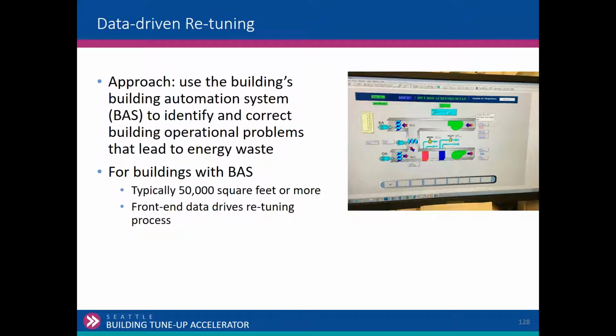So you've got observation-driven and data-driven. Observation-driven, you go out, look at the rooftop unit, and verify that the economizers work. The data side, obviously, is using the building automation system to identify and correct. How many of you are going to be working with building automation systems when you do your tune-up? In that process, you can verify: you can trend data, or you can initiate control action and observe the response. PNNL put together a guide on setting up some of those trend logs to help you with your assessment at the front end. With a BAS building, you're probably going to figure out what you want to trend and what you're trying to assess, and get those trend logs before you complete your assessment. Without a BAS system, you may be figuring out where you're going to deploy loggers to do that.